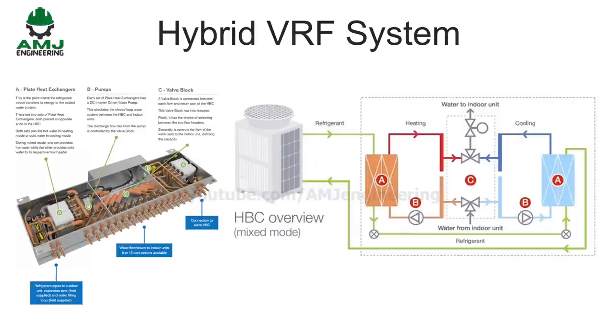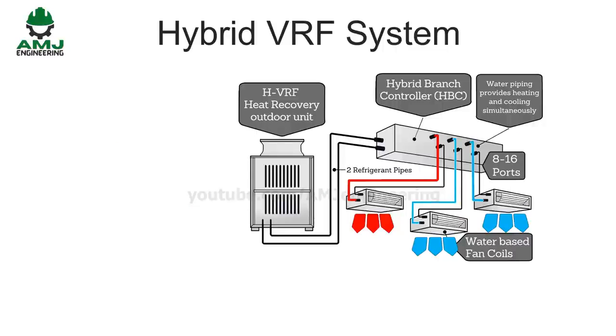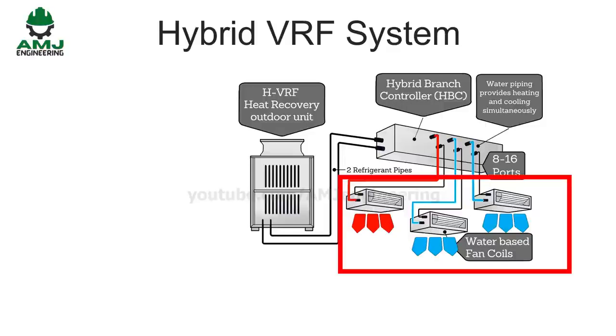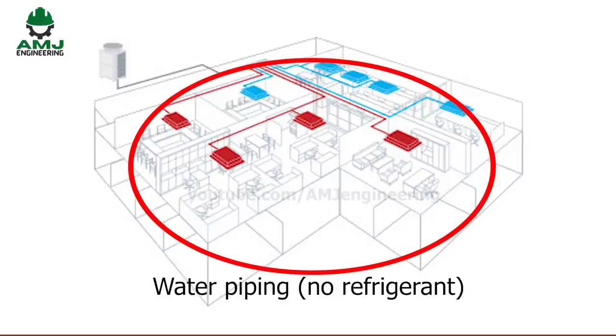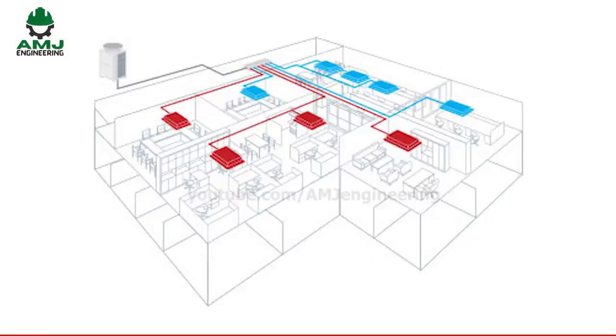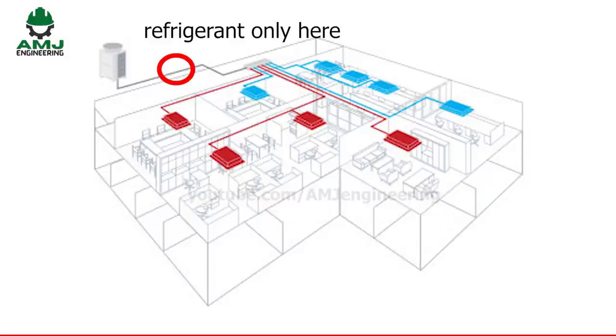The outdoor unit delivers a mixture of liquid and hot gaseous refrigerant to it. This mixture passes through a plate heat exchanger to heat water by condensing the gas, and then the liquid refrigerant passes to a second plate heat exchanger to provide cooling. The key difference between a more traditional VRF and the newer hybrid VRF system is that in a hybrid VRF system, the need for leak detection is removed entirely as it uses water in place of refrigerant in the occupied spaces. Therefore, any risk to occupants and property under the EN 378 guidelines is removed. With F-gas regulations becoming more strict, there's also the benefit that the HVRF uses 30% less refrigerant than a traditional VRF and is entirely R32 compliant.